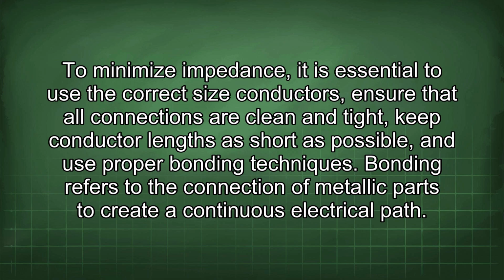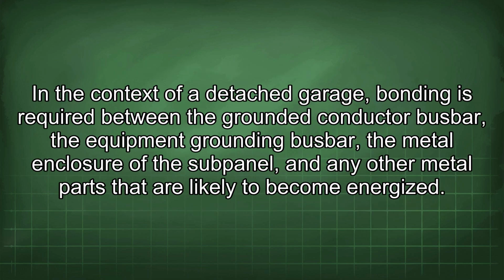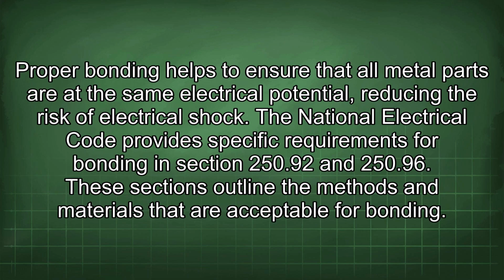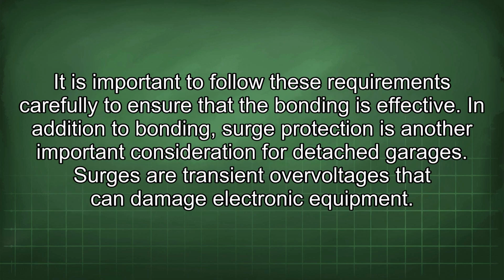Bonding refers to the connection of metallic parts to create a continuous electrical path. In the context of a detached garage, bonding is required between the grounded conductor busbar, the equipment grounding busbar, the metal enclosure of the subpanel, and any other metal parts that are likely to become energized. Proper bonding helps to ensure that all metal parts are at the same electrical potential, reducing the risk of electrical shock. The National Electrical Code provides specific requirements for bonding in Section 250.92 and 250.96. These sections outline the methods and materials that are acceptable for bonding. It is important to follow these requirements carefully to ensure that the bonding is effective.